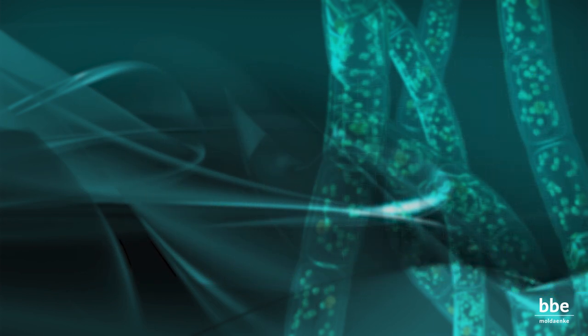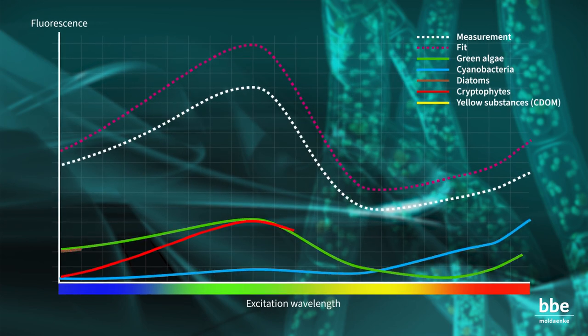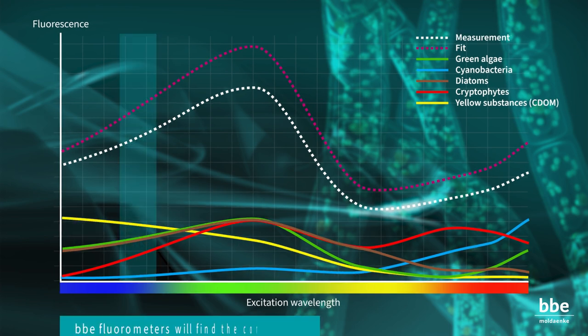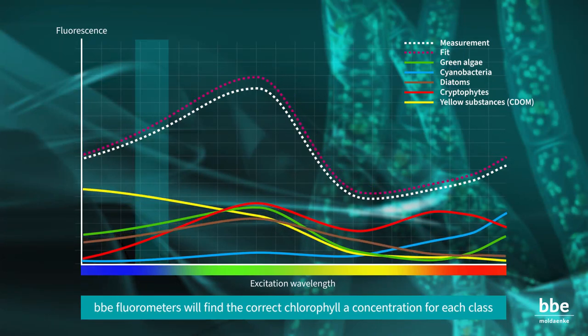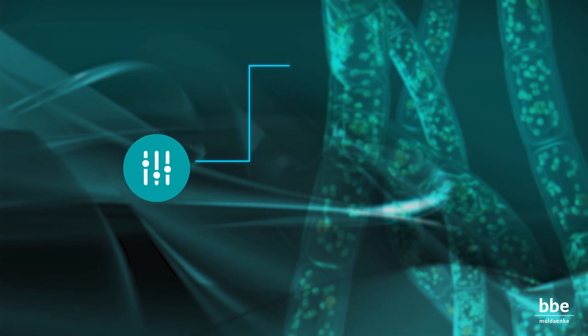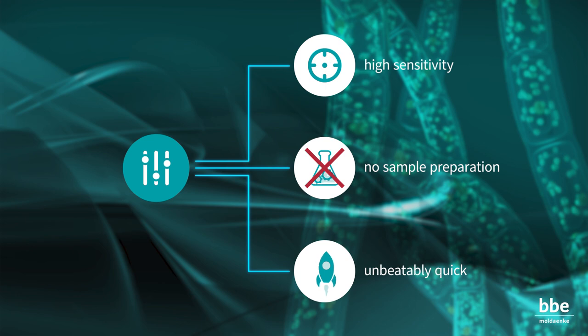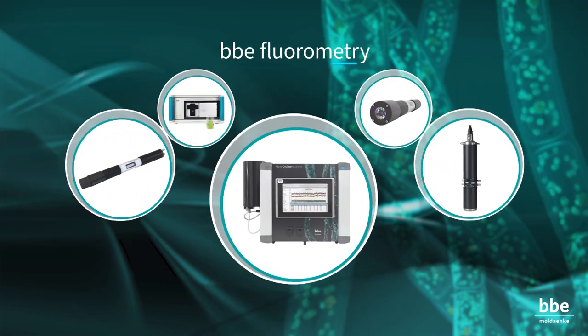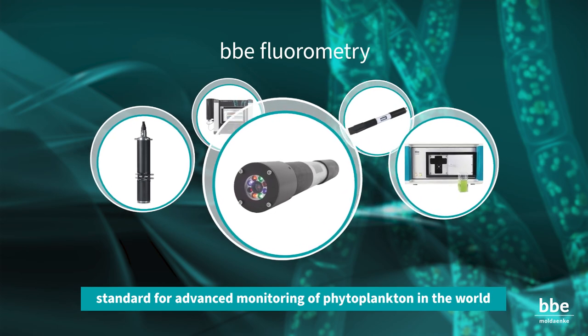A sample taken from a water body will probably contain a mixture of different algae classes. Using the norm spectra of all classes and the yellow substances, the BBE fluorometers will find the correct chlorophyll A concentration for each class. The method has high sensitivity, needs no sample preparation, and is unbeatably quick. BBE fluorometry is the standard for advanced monitoring of phytoplankton in the world.